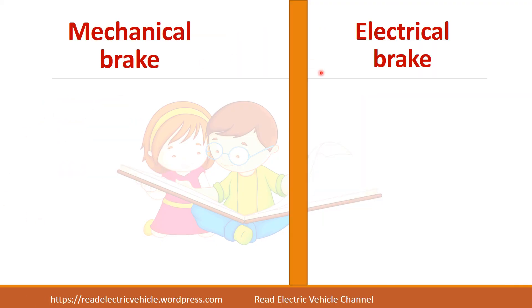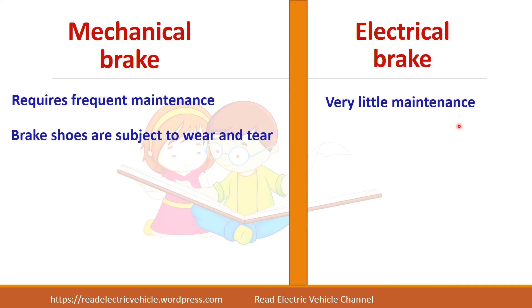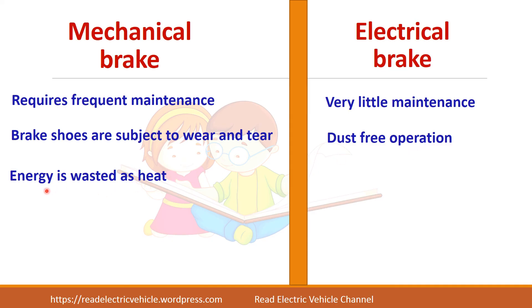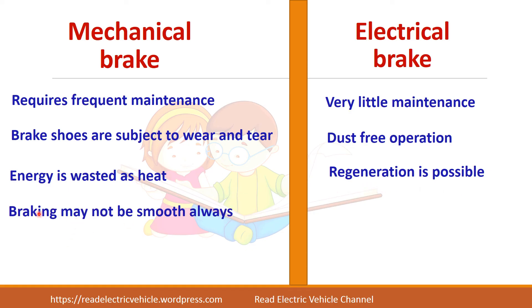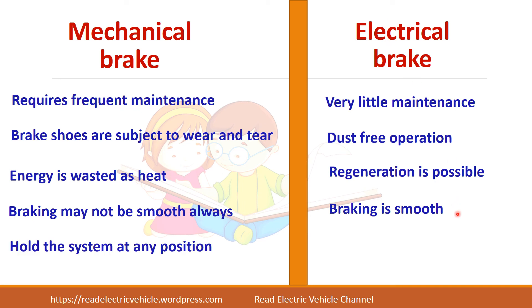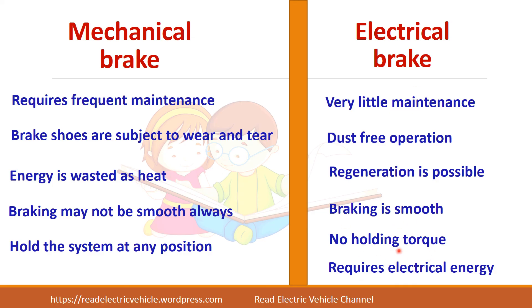The difference between mechanical braking and electrical braking: mechanical braking requires frequent maintenance, whereas electrical braking requires very little maintenance because there are no brake shoes or brake drums, giving dust-free operation. In mechanical braking, energy is wasted as heat, whereas in electrical braking, regeneration is possible. Mechanical brakes may not give smooth operation, whereas smooth operation is possible with electrical brakes. Mechanical brakes are very good at holding the system at any position, but electrical brakes have no holding torque, so normally electrical brakes are used along with mechanical brakes. Additionally, the electrical braking system requires electrical energy.